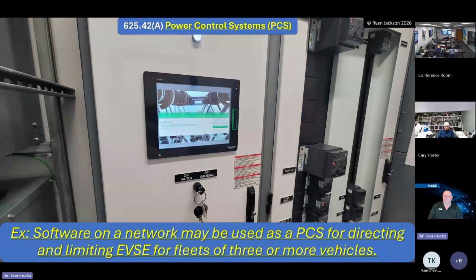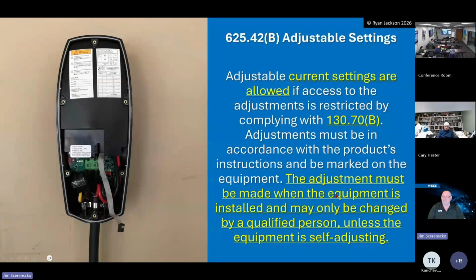Again, if you have a software network and you have a fleet of chargers, you can have limited EVSE fleets for 3 or more vehicles, and the adjustable current settings are allowed if access to the adjustment is restricted by complying with 130.70(B), which is now energy management systems because it got moved to 130. The adjustment must be made when the equipment is installed and may only be changed by a qualified person unless the equipment is self-adjusting.